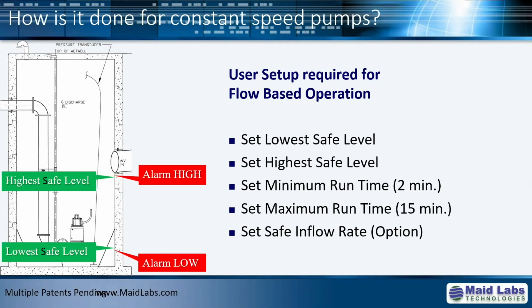So if you click next, the idea here is to move the head higher. When the flow coming in is low, and historically it has been low at that time of day with no rain or anything like this, it's basically safe to run the pumps at a higher level than when the flow rate is high or when you don't know that flow rate. By changing the average head, you're increasing your pump capacity, and by quite a lot.